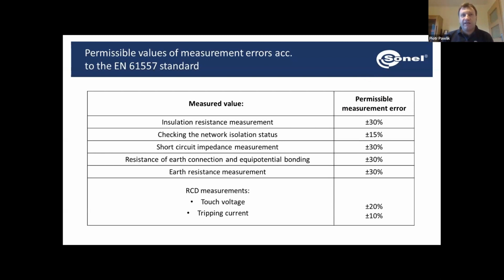And now it is important to look at the technical specs of our meters and check their measuring ranges. Because we can all imagine that the display range on the meter starts from 0 up to a certain level, but the measuring range, including the error defined by the standard, is connected with the accuracy of the meter. So plus minus a few percent of the measurements, plus a few digits in case of the digital meters, but then the values closer to 0 will be carrying uncertainty well higher than the ones described by the standard 61557. So we look at the technical specs of the meters, we check their measuring ranges, and they will never start at 0. They will start at a certain value and go up to the maximum range of the meter. So we need to remember to check those.